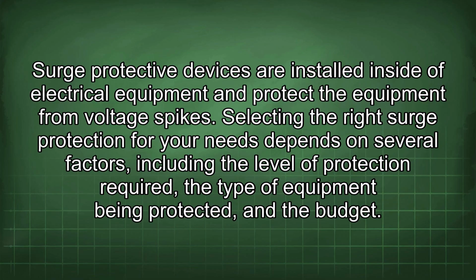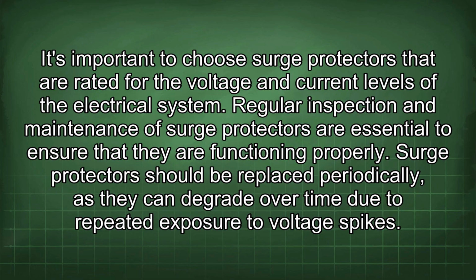Selecting the right surge protection for your needs depends on several factors, including the level of protection required, the type of equipment being protected, and the budget. It's important to choose surge protectors that are rated for the voltage and current levels of the electrical system. Regular inspection and maintenance of surge protectors are essential to ensure that they are functioning properly. Surge protectors should be replaced periodically, as they can degrade over time due to repeated exposure to voltage spikes.